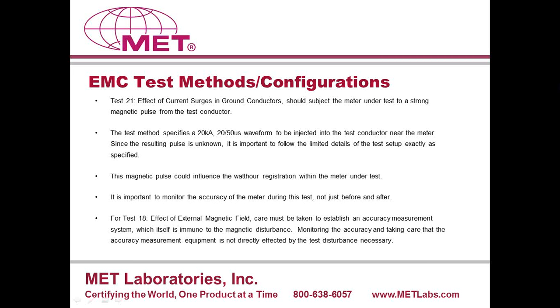So when this test is being performed, you monitor for the accuracy as well as after the testing. You have to make sure that the accuracy measurement equipment that you are using is not affected by this external magnetic field. One other thing that you would also have to consider is to make sure that the current is in phase with the voltage that is applied to the meter device and also to the coil that produces this field.